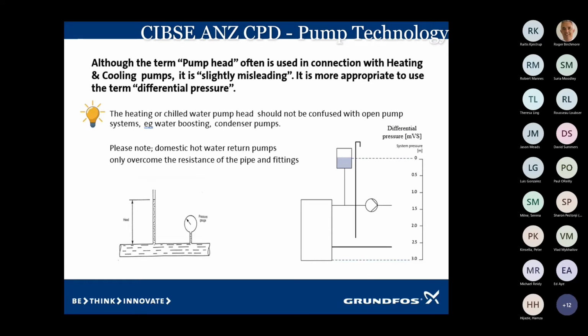The pump head, and some of us get confused, especially if we're learning. 2 systems. We've got an open system and you've got a closed system. In an open system, and it may be pressure boosting, we're boosting water from the basement to the top of the building. In that particular case, we have to measure the static height, and all the losses in the pipework and all the fittings. So that's an open system.